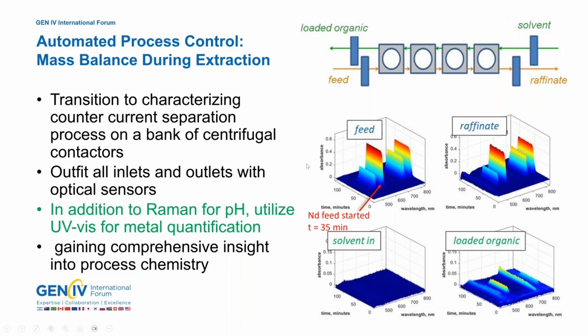At the very beginning, we start with no neodymium in the feed, but 35 minutes into the experiment, we switched over to a feed that contained neodymium. We see an immediate increase in the bands related to neodymium across the UV-vis spectrum until we stopped the neodymium feed at 90 minutes, and then that band dropped back down and continued on to its solvent. In the raffinate position, as soon as we added neodymium to the feed, we had neodymium reporting out to the raffinate, and in the loaded organic we could see the neodymium bands coming in from the extraction of neodymium into the organic phase.